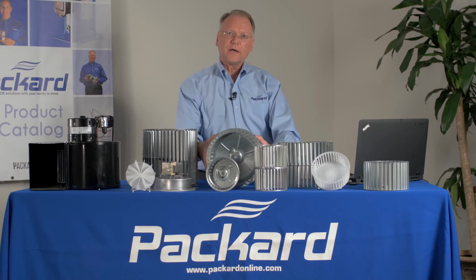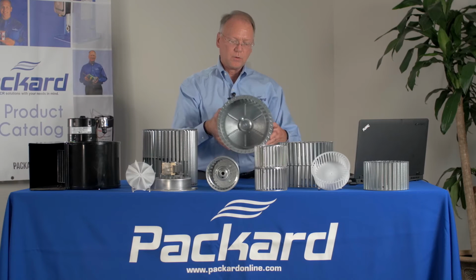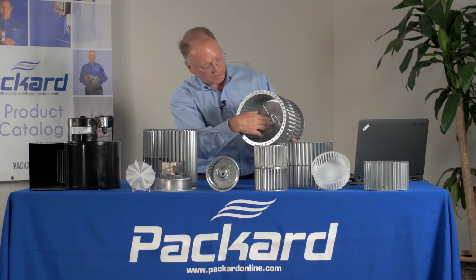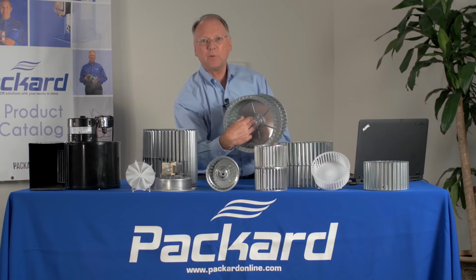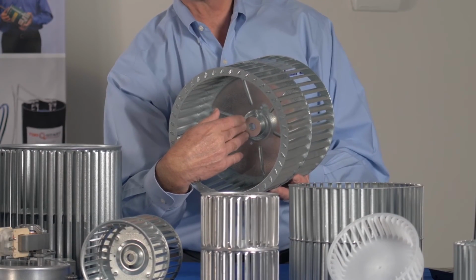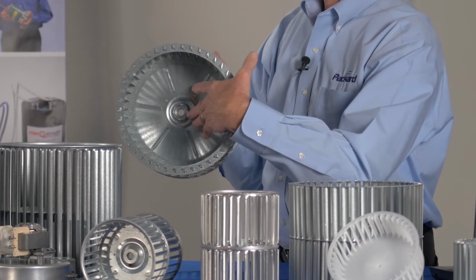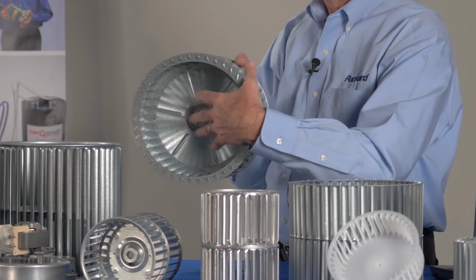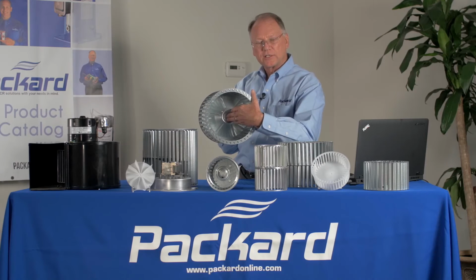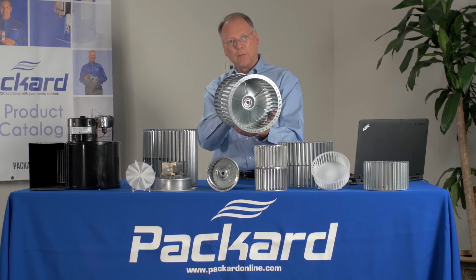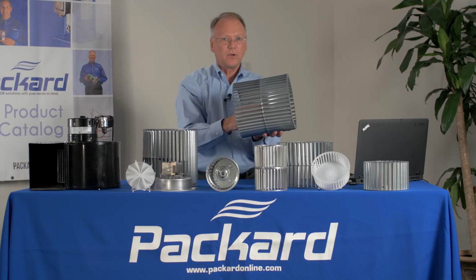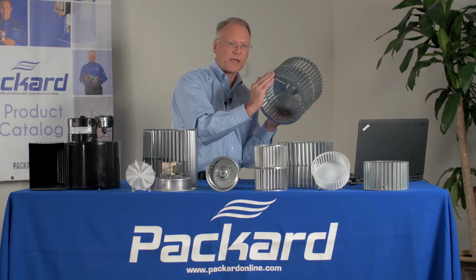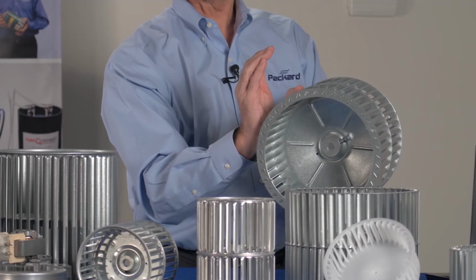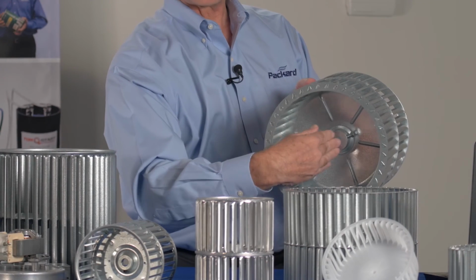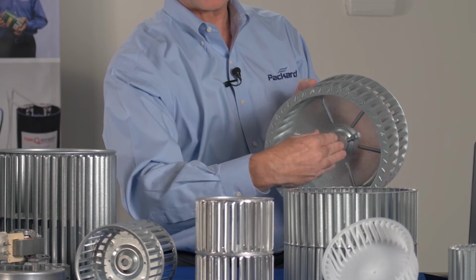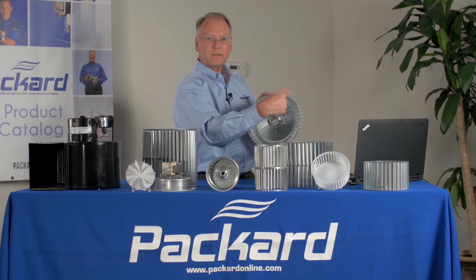On a double inlet wheel, one side of the inlet will have a hub for attaching it to the shaft of the motor. The second inlet does not have a hub. Rotation is determined by looking at the hub, and again, with the curve on the blades. In this case, the curve is like this. Looking at the hub end of the wheel, the rotation would be clockwise.